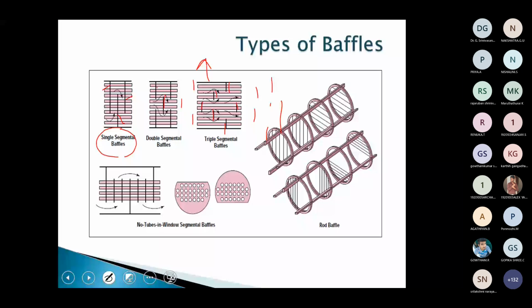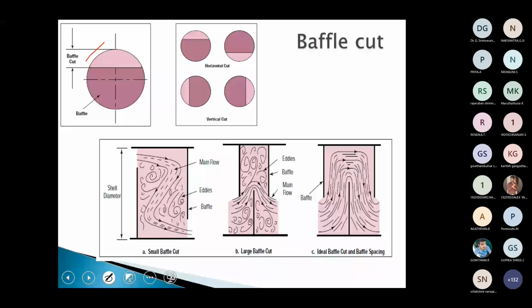And this is the window segmental baffle. Window means there will be no tubes on these sides, the window sides. This is the baffle, and there will be no tubes on the window sides. This is called the baffle cut. Usually, the baffle cut may be in the range of 20 to 25% of the total diameter. That is very important. Usually it is 25%, but based on the fluid it should be 20 to 25%.